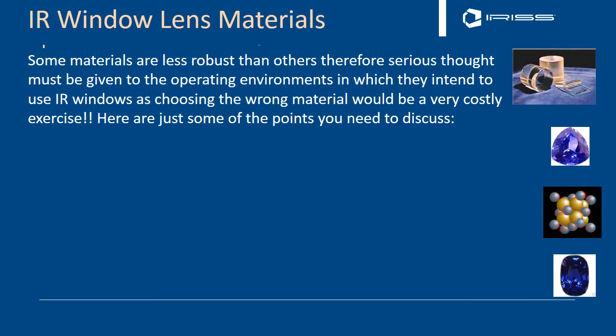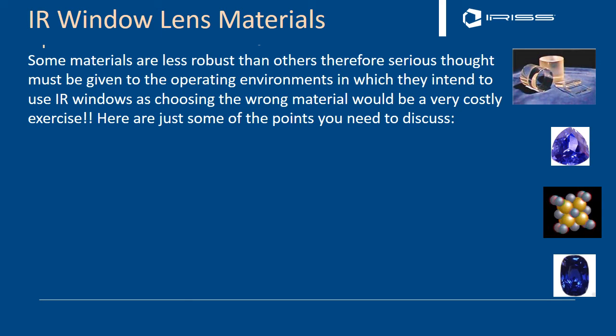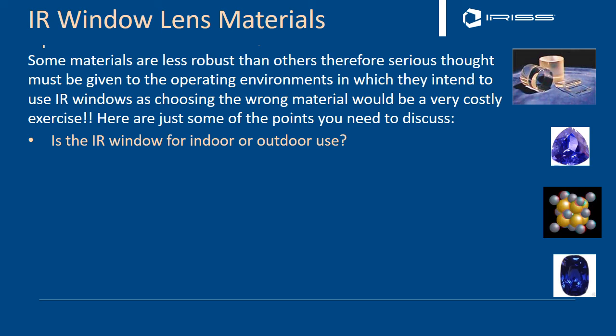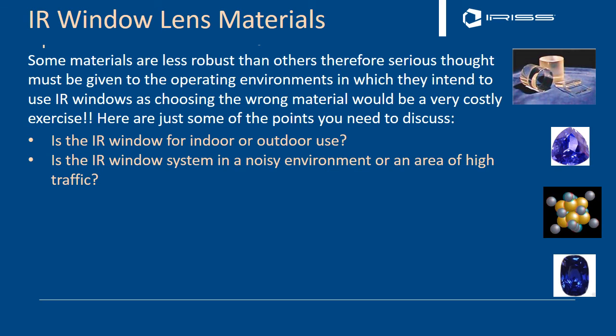When looking at operational considerations for your infrared window, this is very important. Some materials are less robust than others, so give serious consideration to the operating environment in which you're going to place your window — because if you get this wrong it's going to be a very costly exercise. You need to consider: is the window for indoor or outdoor use? Is there an IP rating requirement — for instance IP 65 or IP 67 for outdoor environments? What are the materials of the window body — aluminum, stainless steel, plastics? And is the window system going to be in a noisy environment or an area of high traffic where it can be hit?